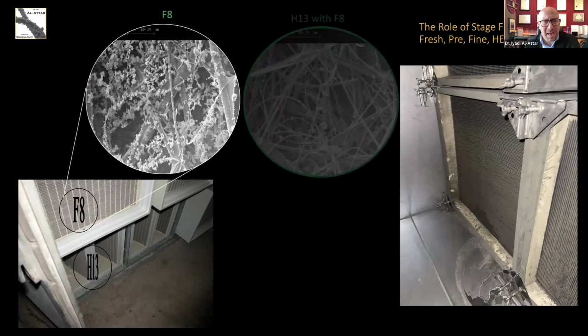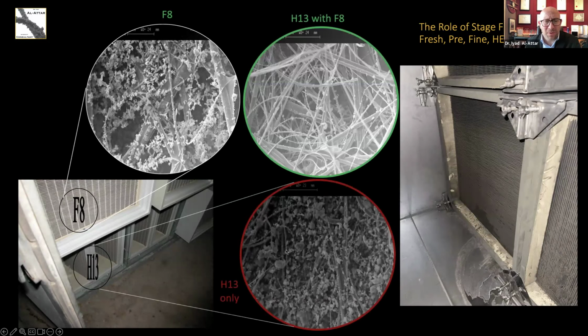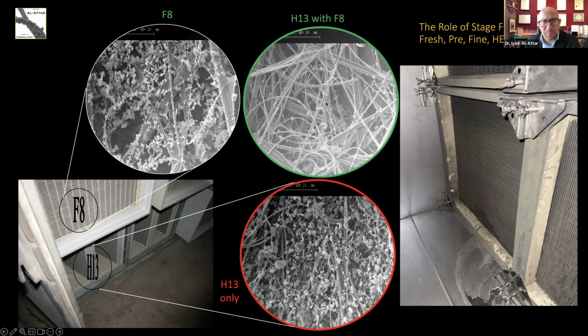This is an experiment I did earlier. You can see four stages of filtration, with the last two stages being F8 and H13. In the absence of an F8, you can see the HEPA filter here is loaded with a lot more particles and concentration compared to the other HEPA filter that was protected by an F8, which had good pre-filtration.